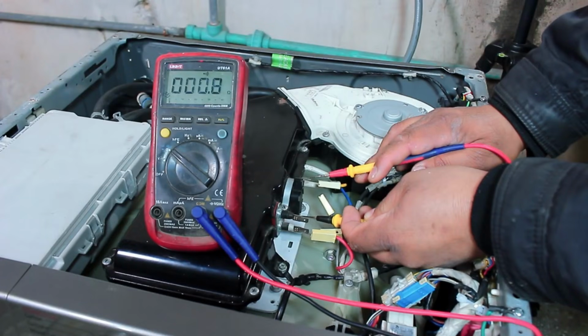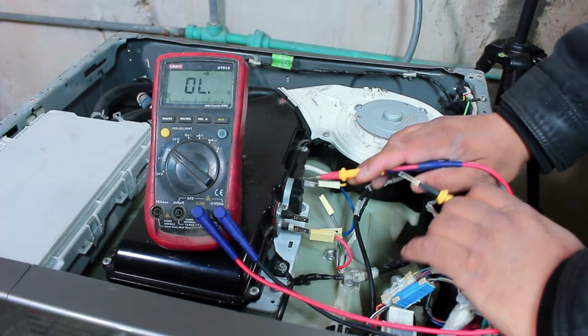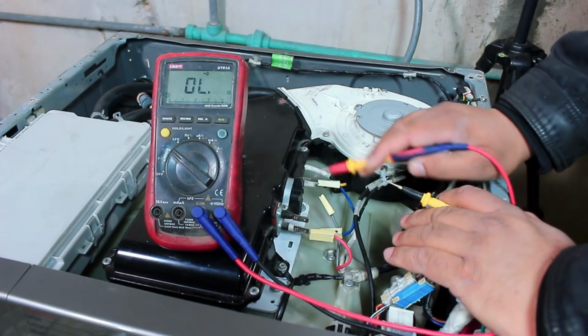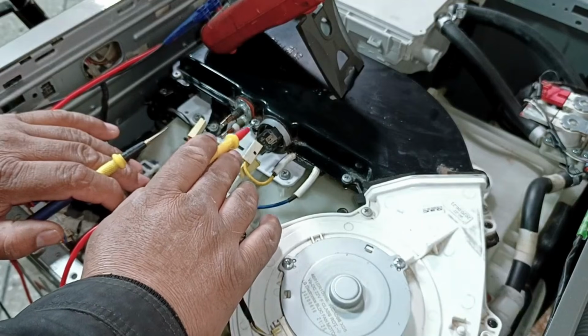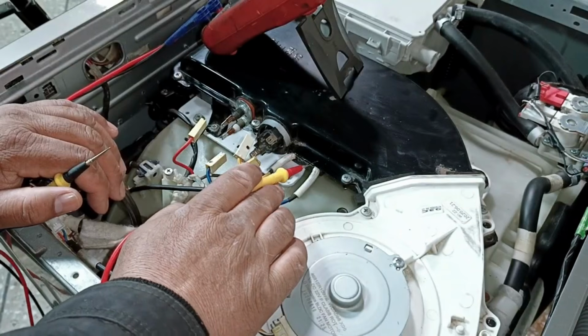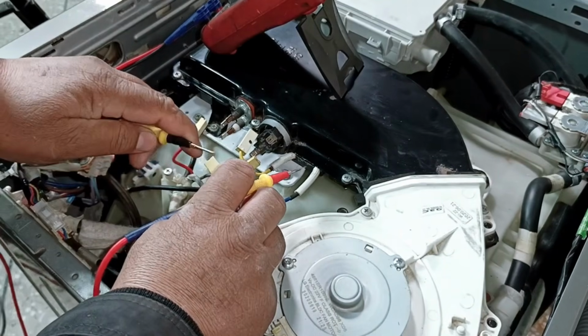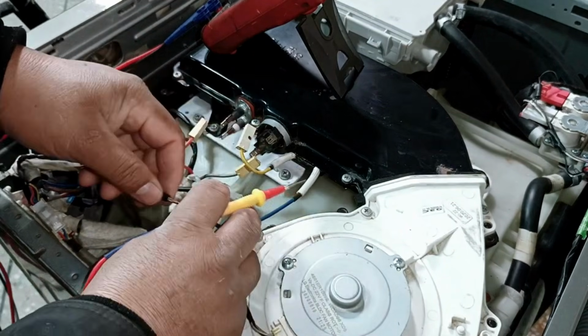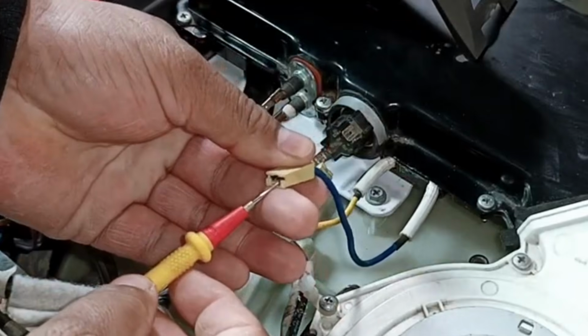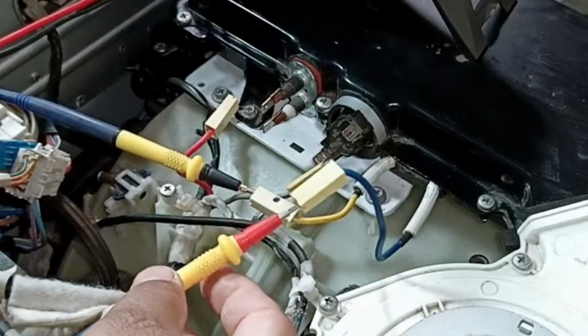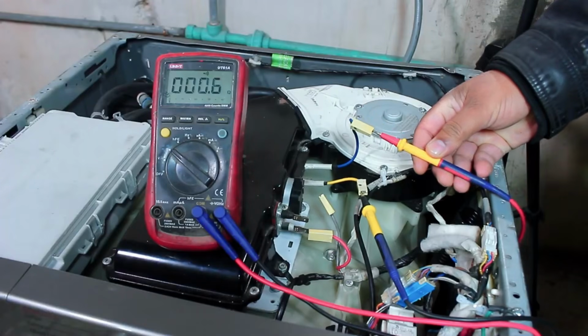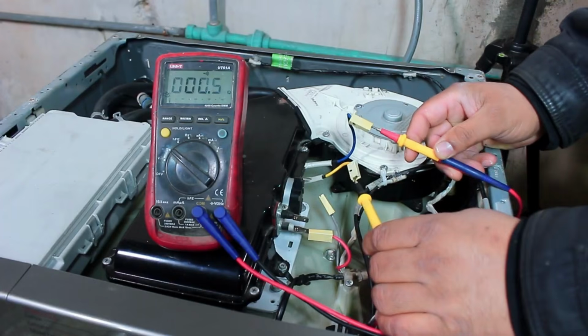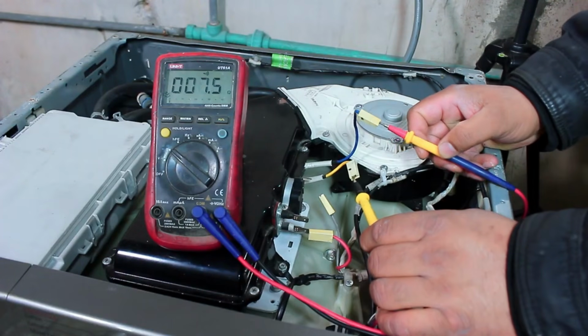If it does not beep, that means the internal contacts are disconnected or open. In that case, the thermostat needs to be replaced. Next comes the bimetal thermal fuse. The method to check it is the same. I will place one probe on one side and the other probe on the second terminal. As you can hear, it is giving a beep sound, which means the thermal fuse is perfectly fine and there is no issue with it.